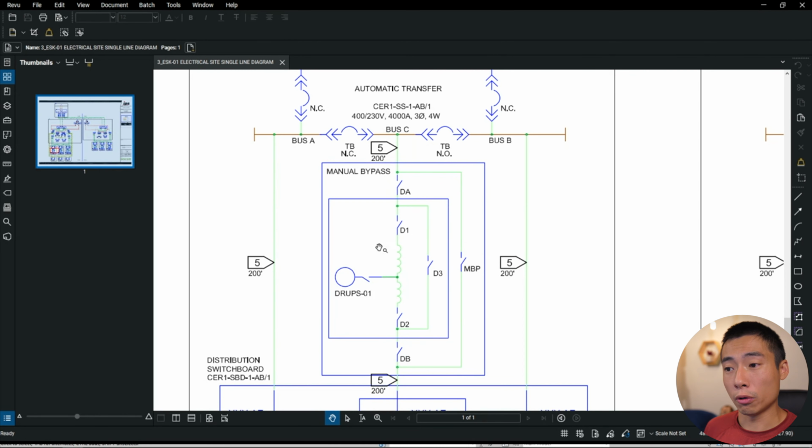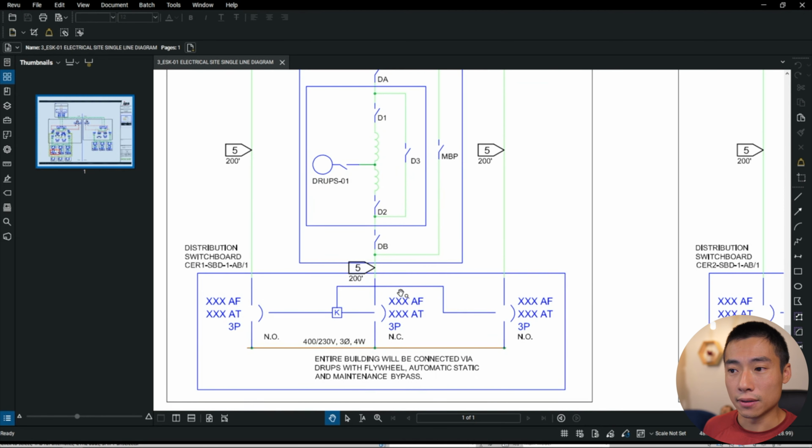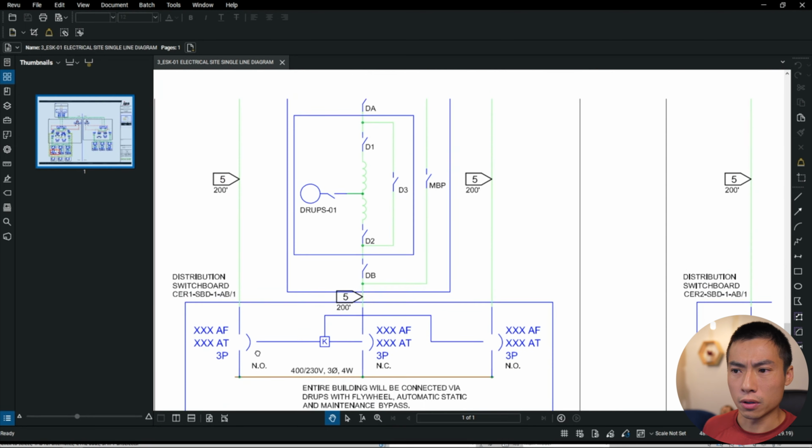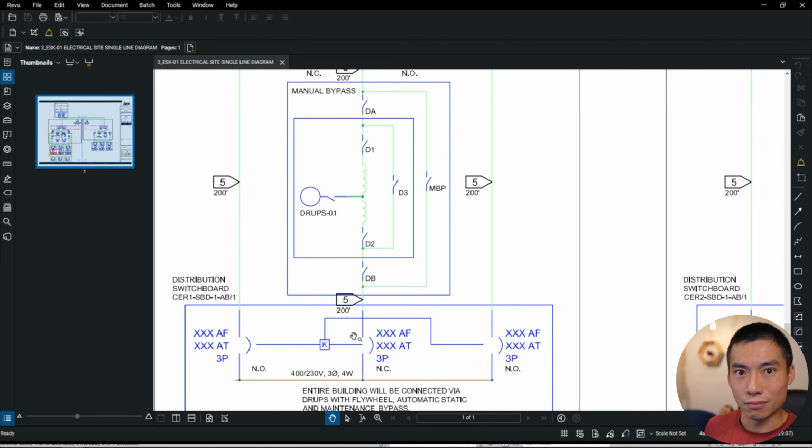This is a diesel rotary UPS that feeds your switchgear, or we said switchboard here. We had a switchboard after the rotary UPS that feeds all the production line equipment. This building couldn't be down. If you lose power for 5 seconds, they basically say, yep, there goes $2 million. So they are willing to invest a lot of money into this infrastructure. Well, willing, but not willing enough. When we gave them the design to price it, they couldn't stomach the cost.